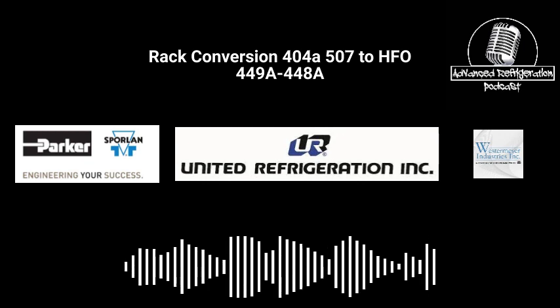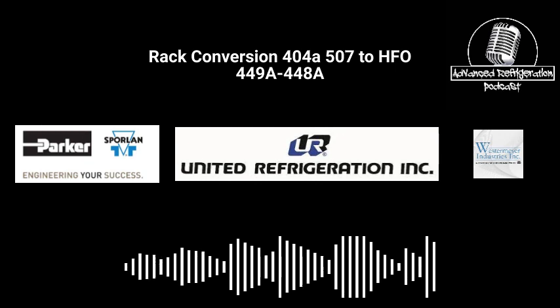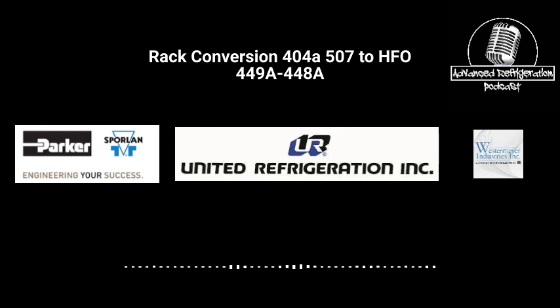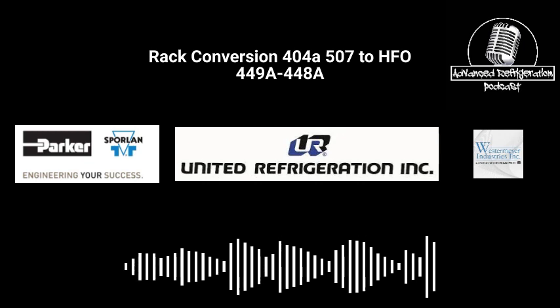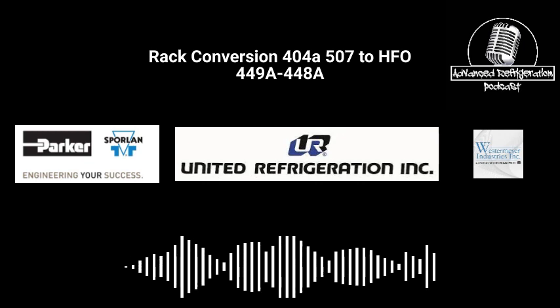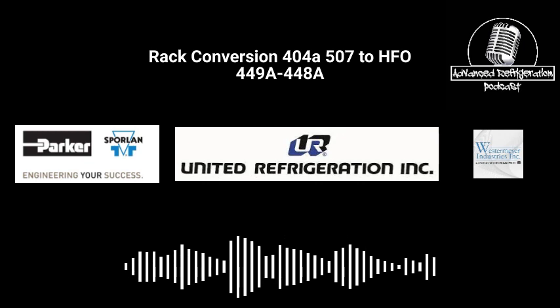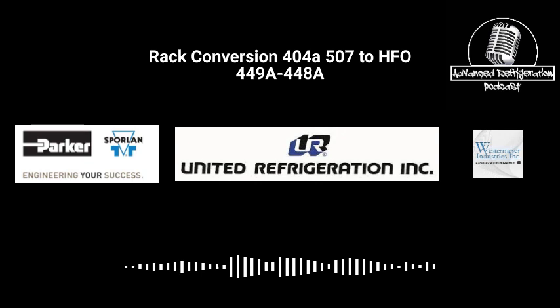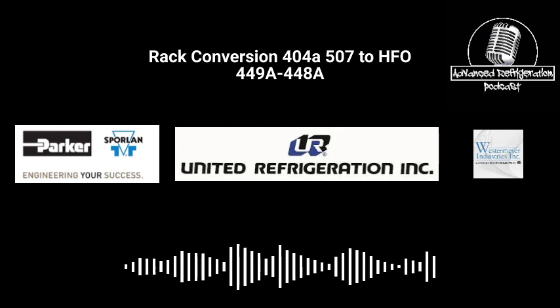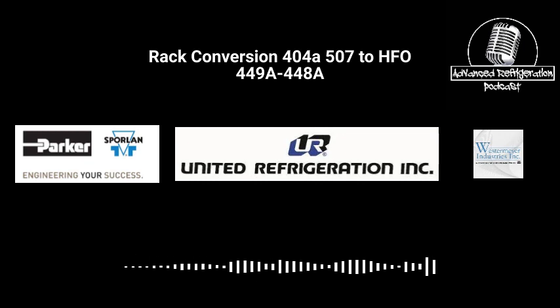I can do probably an island an hour or a row of cases an hour, sometimes more. I'm doing like 10, 12 valves at the same time, so I'll run through these fast. So I'm not really worried about having to go through. But generally, the night of the changeover while it's pulling a vacuum, I'll have those guys go in there and run all the valves back in 2 turns, so that we're not flooding out when they start putting all this refrigerant in there.